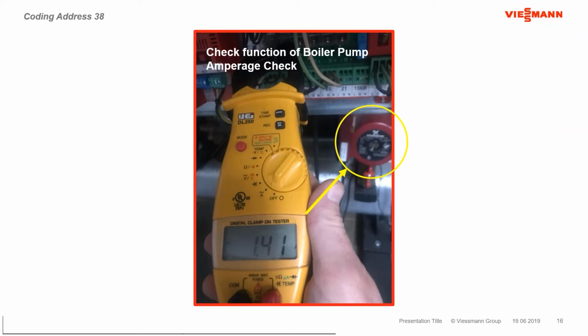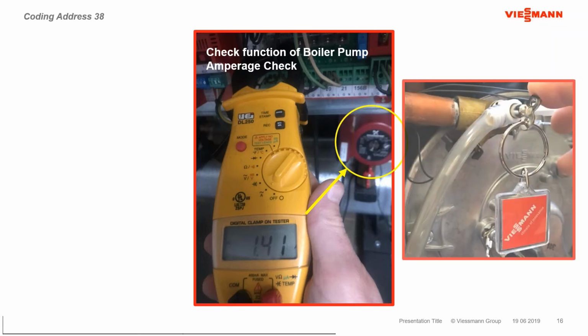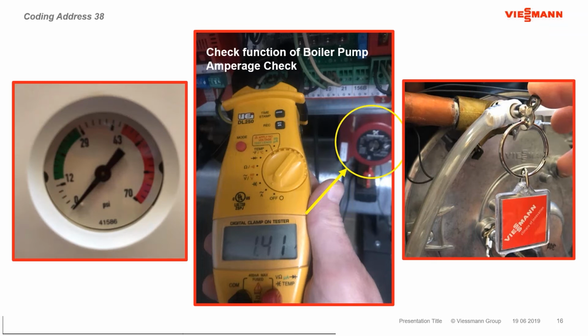But I'm just checking the amp draw on this little pump to make sure that it's functioning correctly. You also may want to, you might have air in your system, so you can use the number one keychain in the world. I think now number one in the world, if I'm not mistaken, Mark, is the Viessmann keychain. I think it's pretty close. We have a number of them out there. Yeah. Or check your pressure.